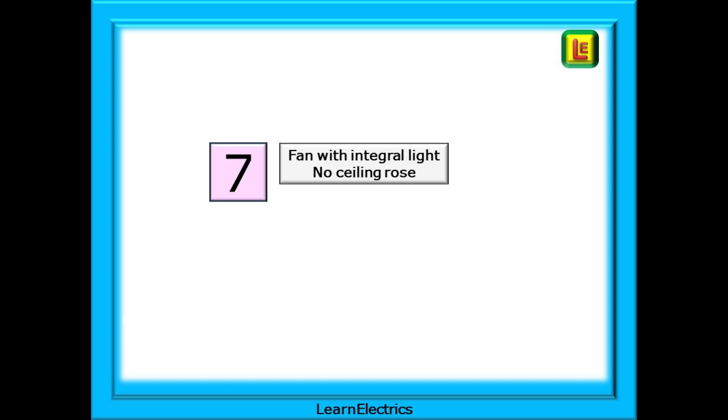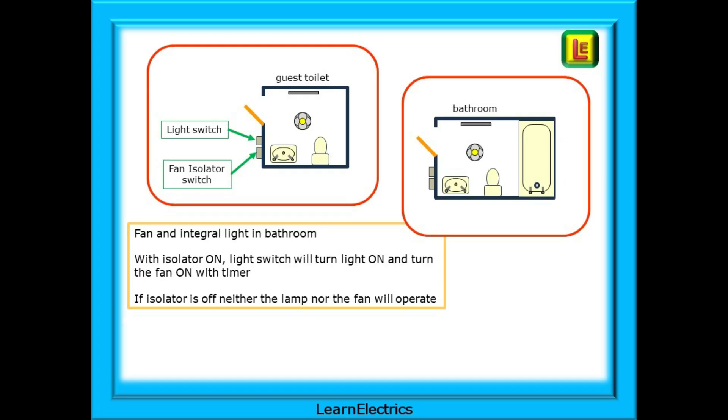And lastly number seven, a fan and an integral light where there is no ceiling rose. I came across this in a house with a small guest toilet downstairs. There was a centrally mounted extractor fan and light combination. The second example was a small bathroom in an older property with the central fan and light combination. With the isolator on the light switch will turn the lights on and turn the fan on with the timer enabled. If the isolator is off neither the lamp nor the fan will operate.